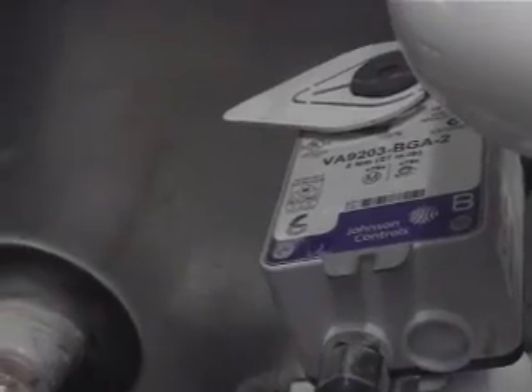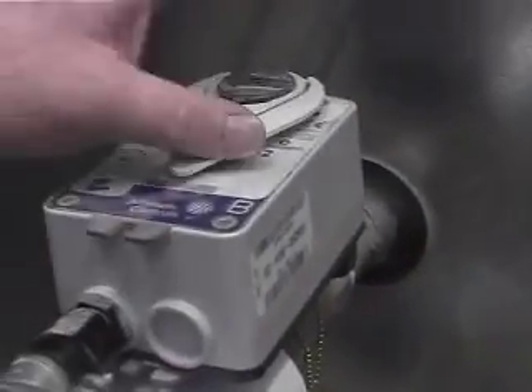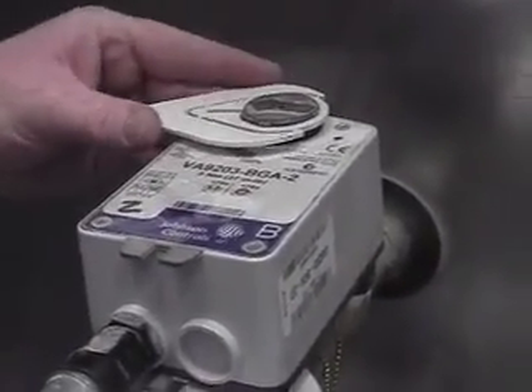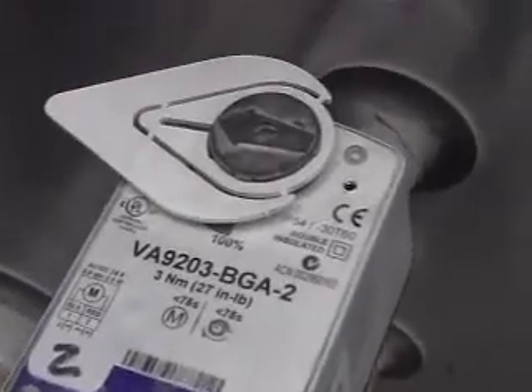So this would be the makeup valve, this one. This is the makeup valve. That will be consistently open whenever the system's enabled to run. And this one would be shut. One thing to note with these valves, don't pay attention to the white thing because it spins. You just gotta look at the little black one, okay? Exactly, that arrow is the indication of the position. Generally you'll probably have a little bit of water bypassing through that you can hear. The pump has a little bypass, so you're always pushing fresh water through it.